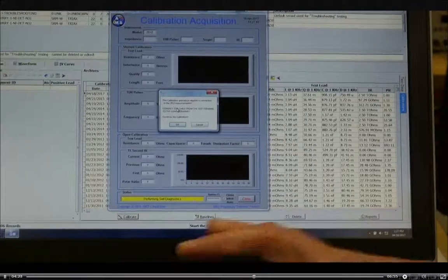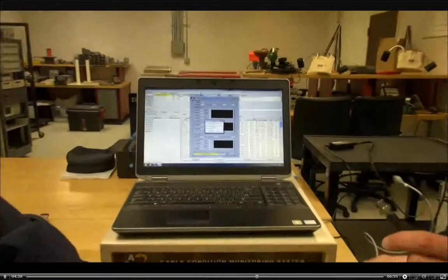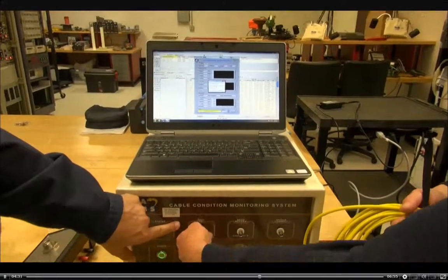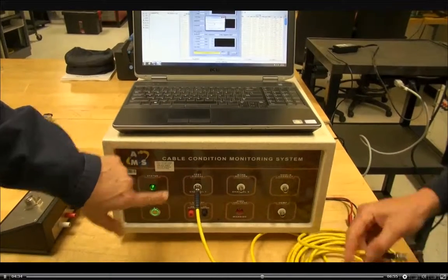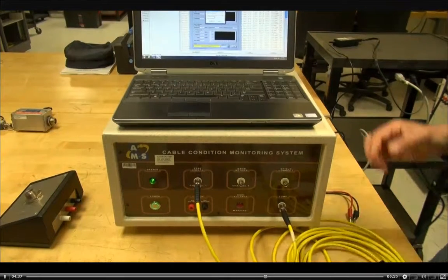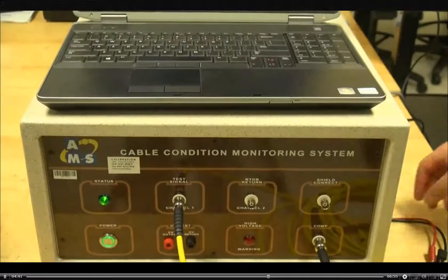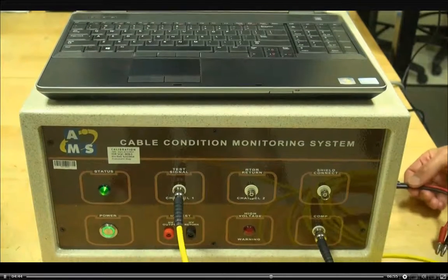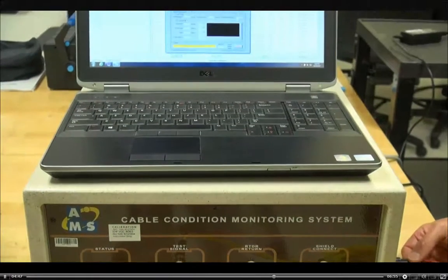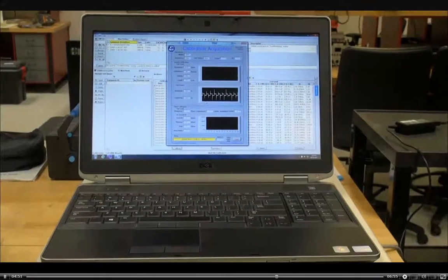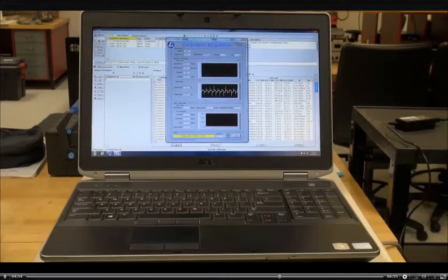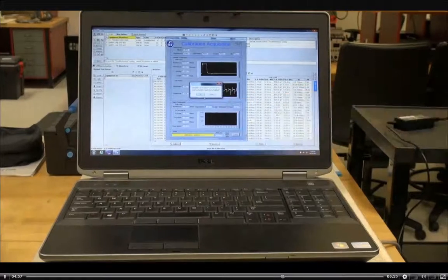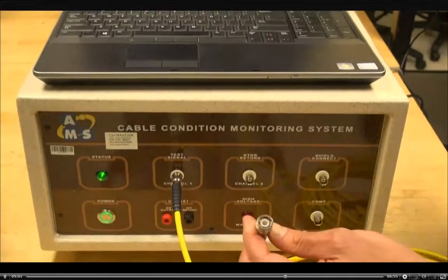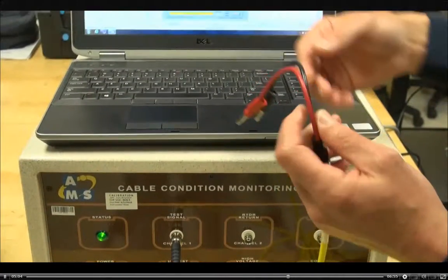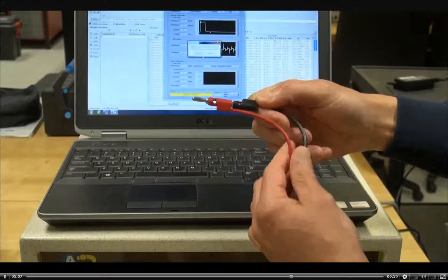Alright, now it says connect the test cable from the test terminal to the comp terminal. So down on the CCM system, we're going to hook up our test leads from the test signal jack to the comp jack. And press OK. Alright, now it says disconnect the test cable from the comp jack and connect your test clips. And it says to short them. So we got our test clips we're going to use, we're going to short them together. Hit OK.